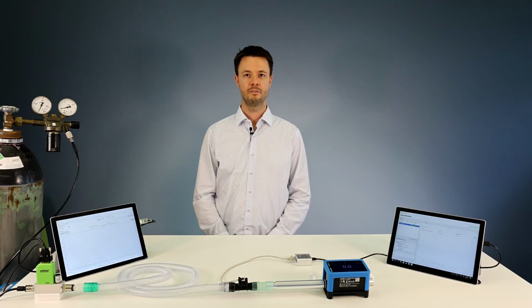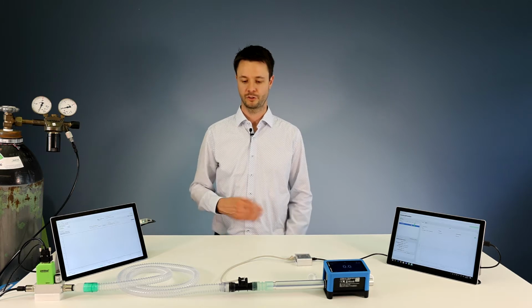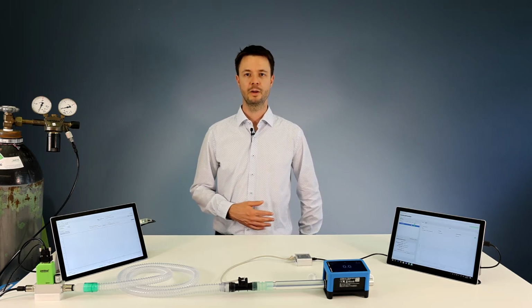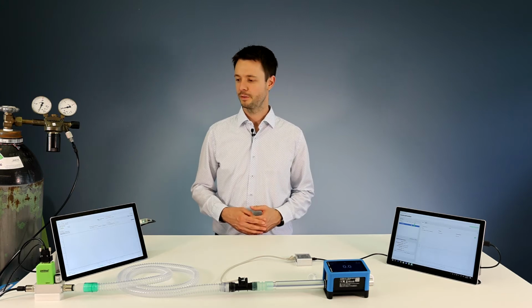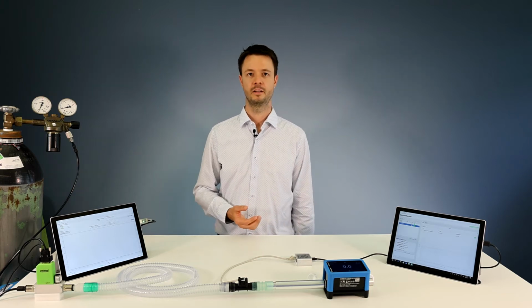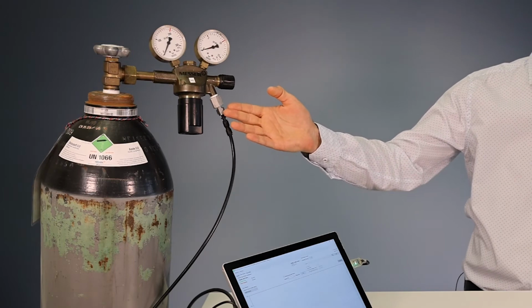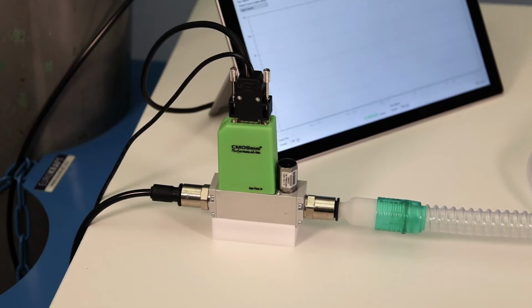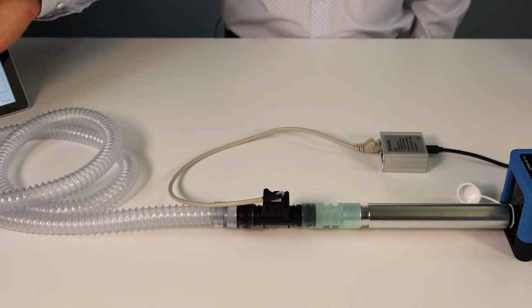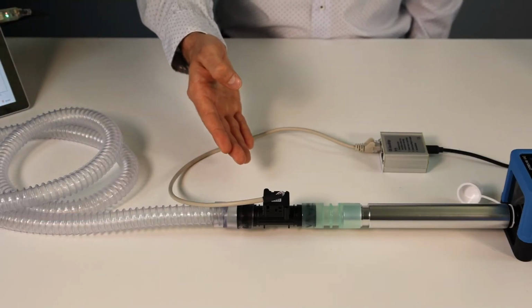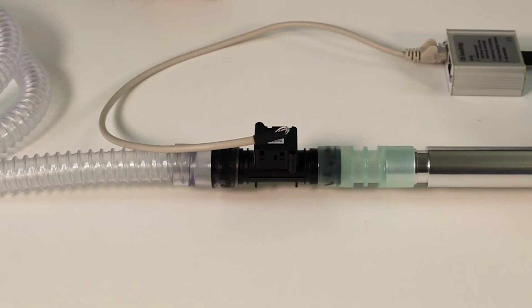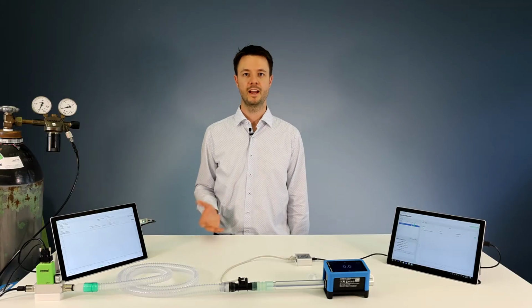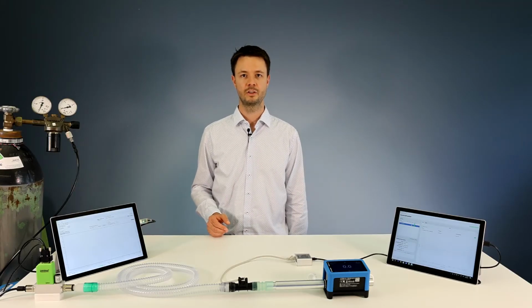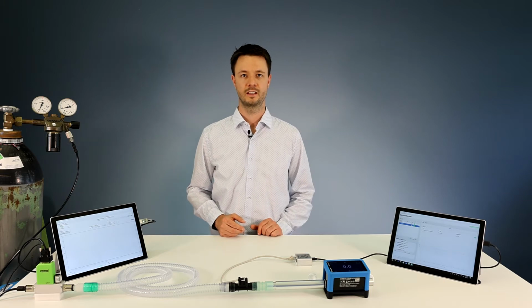In this video, we'll have a look at how to successfully perform first tests with flow sensors and what to pay attention to. For this purpose, I've prepared the following test setup. We'll use pressurized air from this gas bottle and regulate flow with Sensirion's SFC 5500 mass flow controller. Downstream, we have the flow sensor which we want to test. I have here an SFM 3003 flow sensor. But you can use any of Sensirion's inspiratory, expiratory or proximal gas flow sensors in this setup.